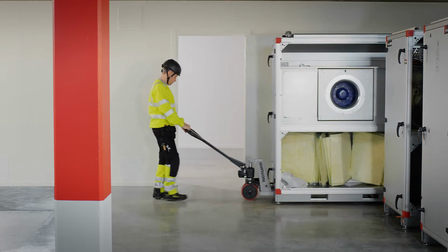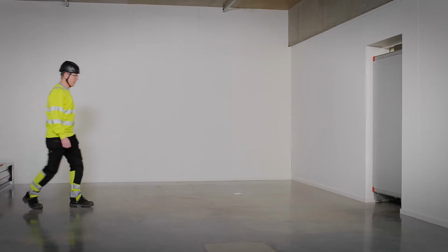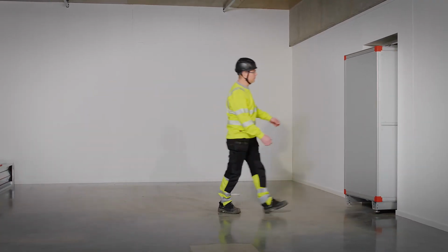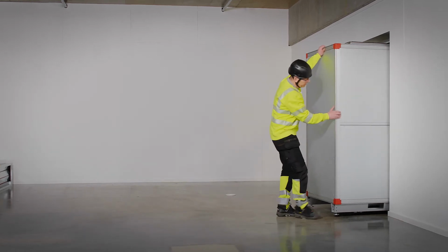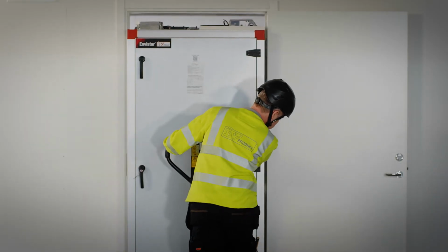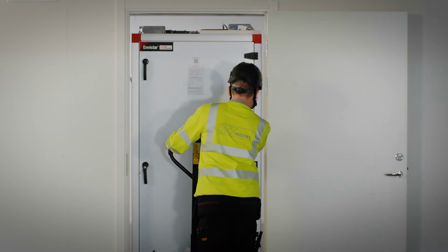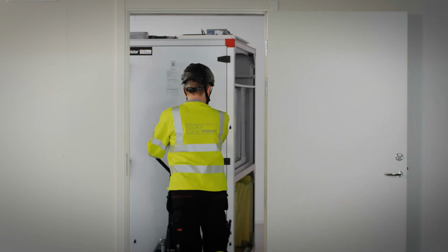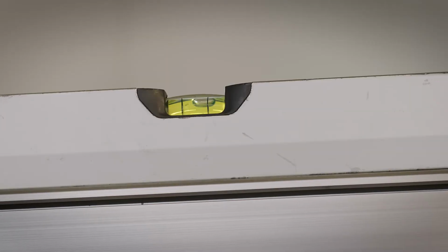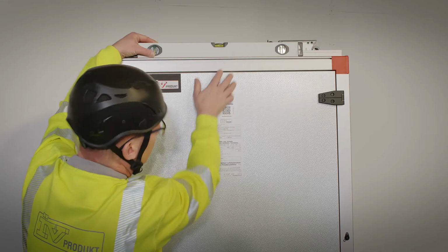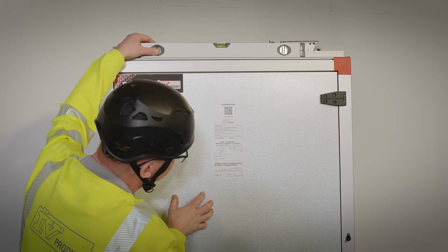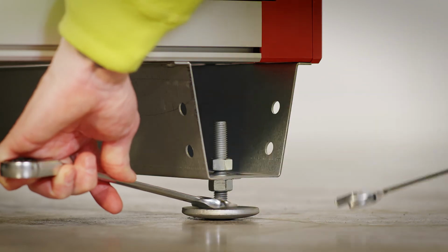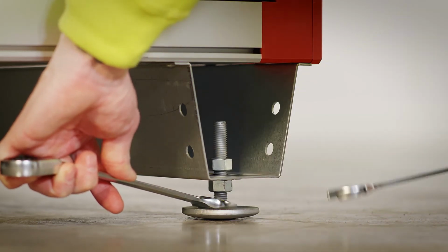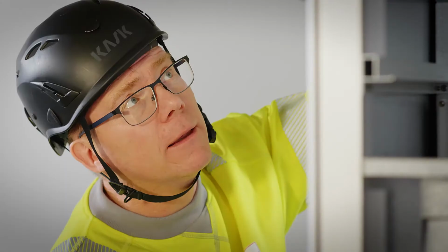It's now time to transport the first section, which in this case is a fan filter section. Make sure the unit is level by adjusting the feet. Lock the rear feet, as they will be difficult to access later once it is completed.